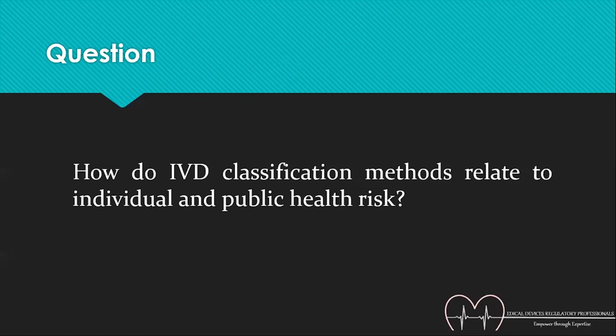That said, for IVDs, as they deal with human specimen, the way they are classified in certain regions may vary. For example, in the EU, the rules to classify IVDs are different compared to how you classify general medical devices. Now you have A, B, C, D as against 1, 2A, 2B, and 3 for classifying IVDs. One point I would like to highlight, which is specifically applicable to IVDs, is whether the device is for home use or not. The device classification may vary. For example, a glucose monitoring system, which is claimed to be used at home versus for professional use, might have a different classification, and the route for conformity may also vary.